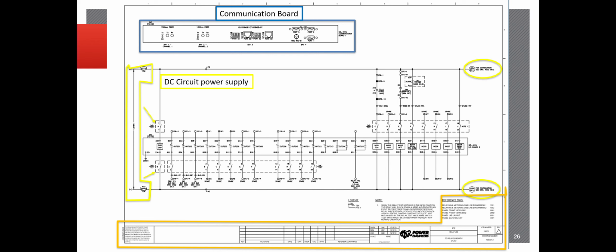To the right, these circles are pretty much continuations. So if this drawing can't fit all the equipment that may be on the DC circuit, this circuit specifically, they'll just reference another drawing so that you know this power supply to the left will not only feed this relay but possibly something else on a different drawing. It's extremely important to catch those and verify the other equipment is rated for 125 volts DC as well before you turn it on.